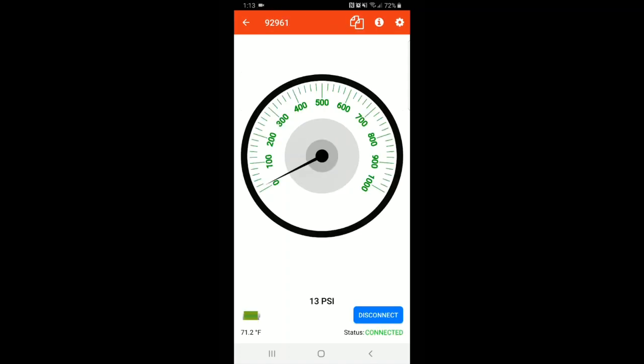We currently have the pressure transducer connected to a control valve. For the purposes of this demonstration, we are simply going to actuate a function and then come back out of it by means of the control joystick. You can see here that I have the pressure gauge on the screen turned down to 1000 psi as we are working on a relatively low pressure circuit. When we actuate the function, we see the pressure slowly begin to build as we get further and further into the joystick. And as we come out of the joystick, you will see the pressure begin to dissipate back down to the starting value. Once again, this is all completely wireless. I am currently standing roughly 30 feet away from the control valve.